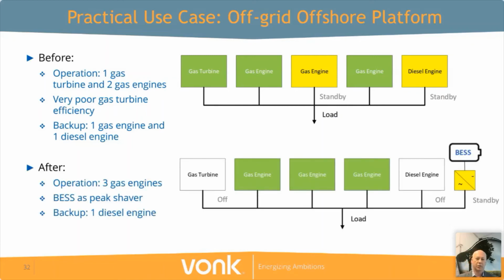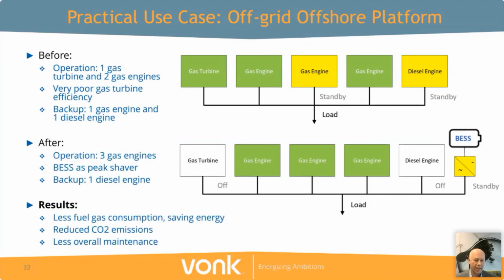You can take the gas turbine out of operation. Also, you do not need the diesel engine anymore for the backup, because you already have the battery energy storage system in place for that. And the battery energy storage system will cover your peak loads. So it acts as a peak shaver, or also called a spinning reserve. This is a nice example. The results again are less fuel consumption, saving energy, reduced CO2 emissions, and less overall maintenance.